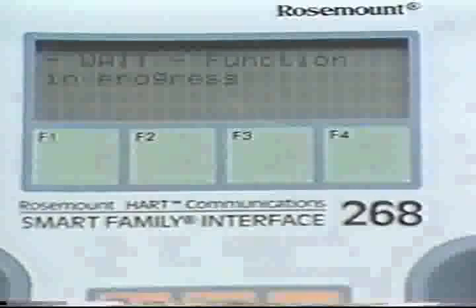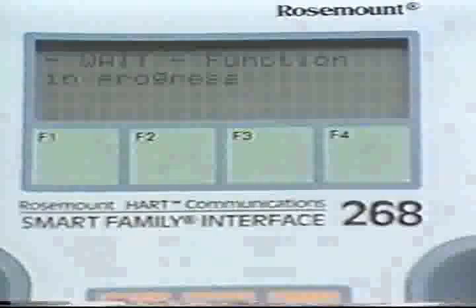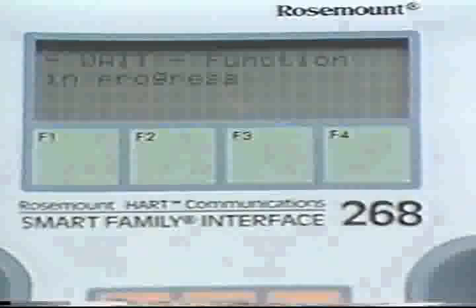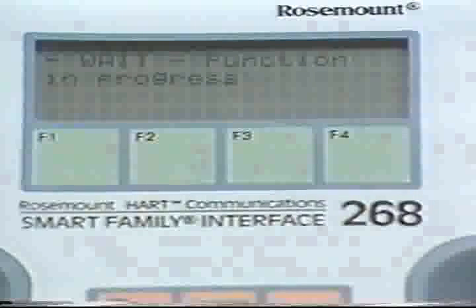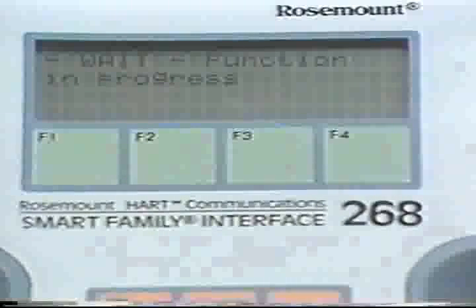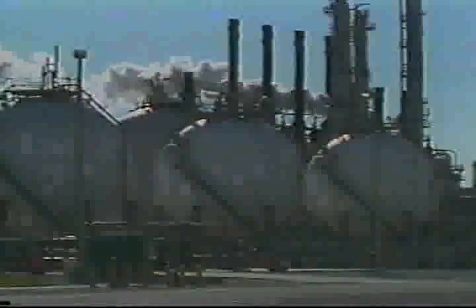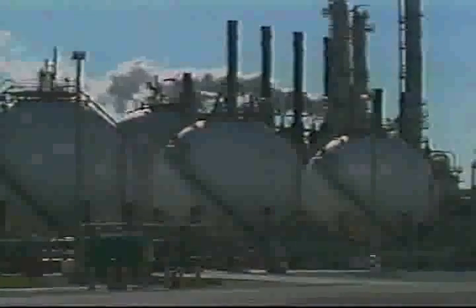Once you understand how the interface device works, calibrating a smart mass flow meter is easy. Since process fluid is necessary to the calibration procedure, this instrument is usually field calibrated. Mass flow meters are versatile instruments, and for this reason they're used to measure many different process fluids. Smart mass flow meters make changes like modifying the instrument range simple and convenient. In the next segment, we'll begin looking at instruments that measure level and their calibration. But for now, stop the tape and review what you've seen here.